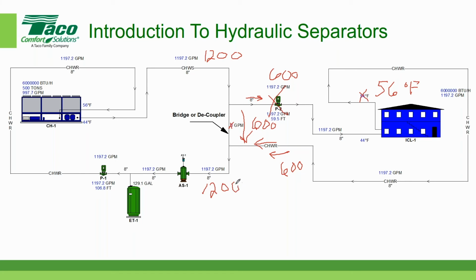Okay, so now, based on the temperatures that I have in this system, if someone could type in, what is my supply water temperature just before I get to the hydraulic separation or the bridge? What's my water temperature right there? Anybody want to type in and tell me? 44 degrees, a lot of people are typing in here. All right, 44. Now, if that's 44 degrees and there is a 12-degree rise, then the return water temperature is coming back here at 56 degrees.